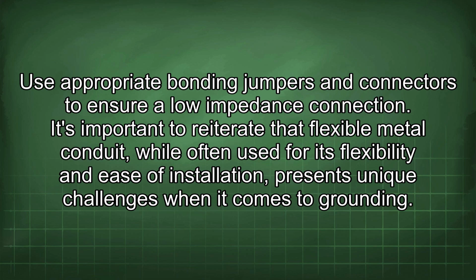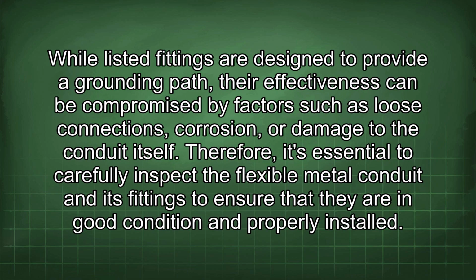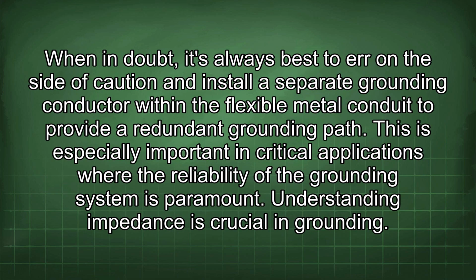It's important to reiterate that flexible metal conduit, while often used for its flexibility and ease of installation, presents unique challenges when it comes to grounding. While listed fittings are designed to provide a grounding path, their effectiveness can be compromised by factors such as loose connections, corrosion, or damage to the conduit itself. Therefore, it's essential to carefully inspect the flexible metal conduit and its fittings to ensure that they are in good condition and properly installed. When in doubt, it's always best to err on the side of caution and install a separate grounding conductor within the flexible metal conduit to provide a redundant grounding path. This is especially important in critical applications where the reliability of the grounding system is paramount.